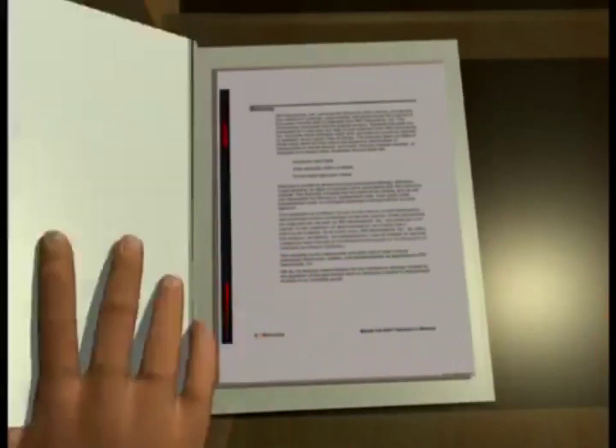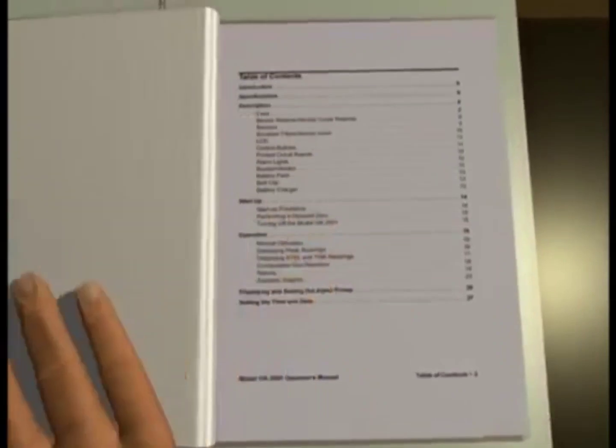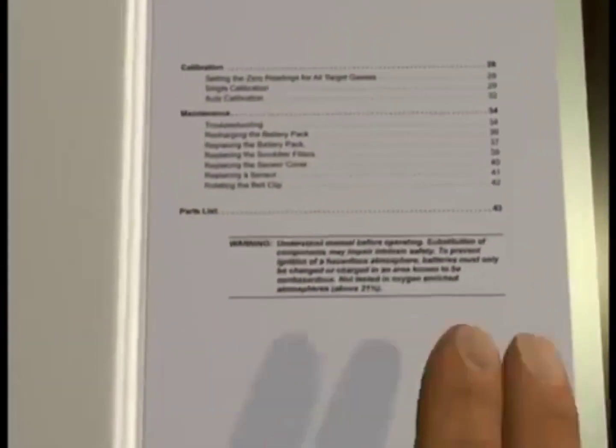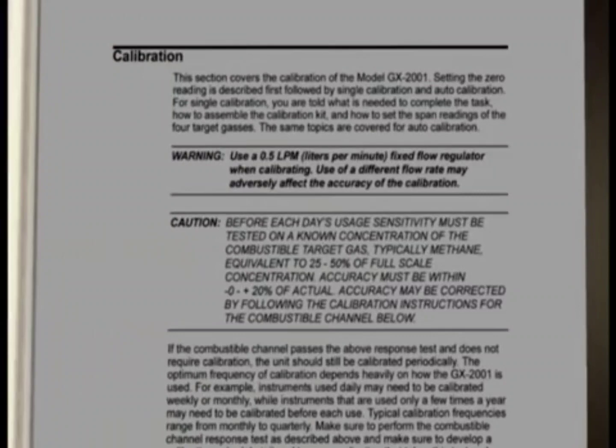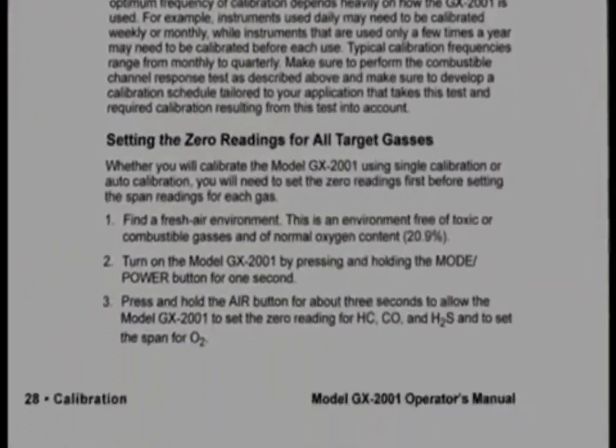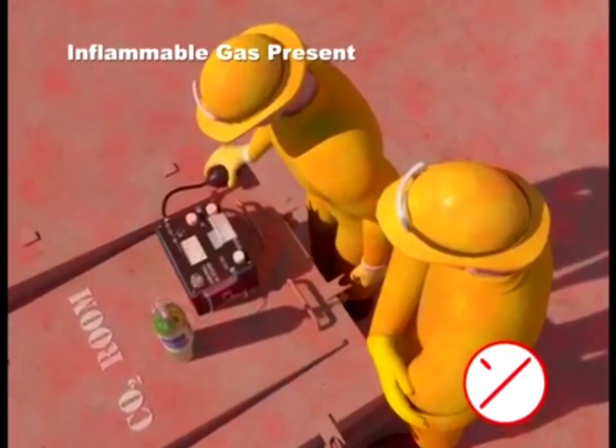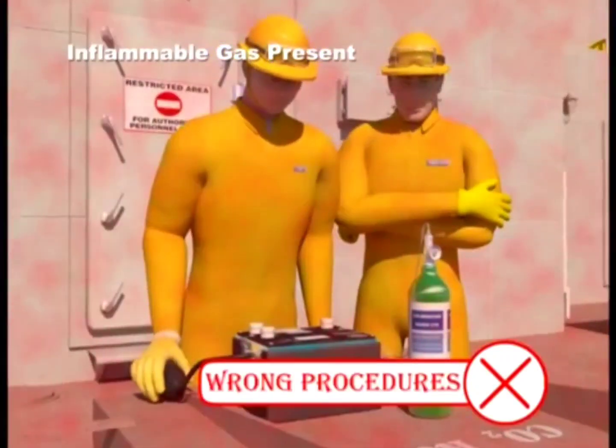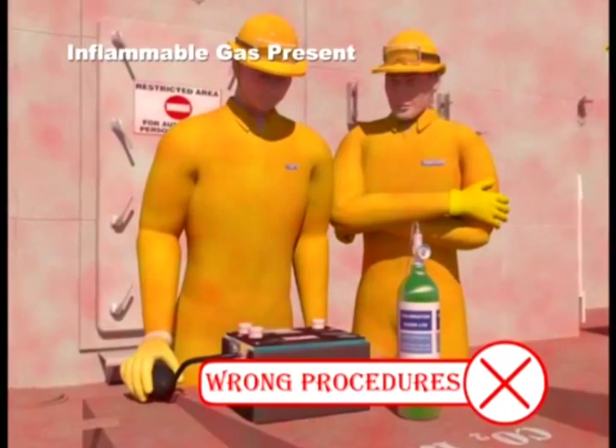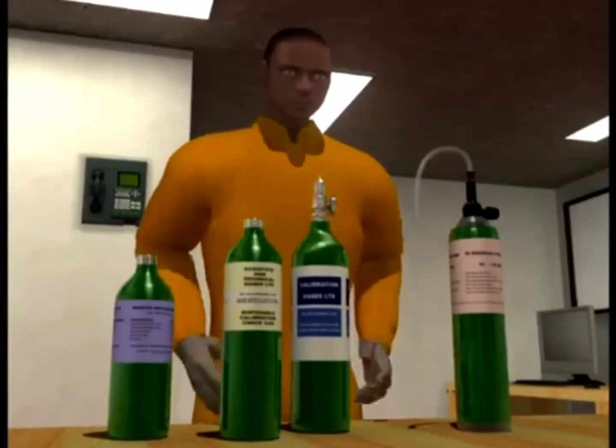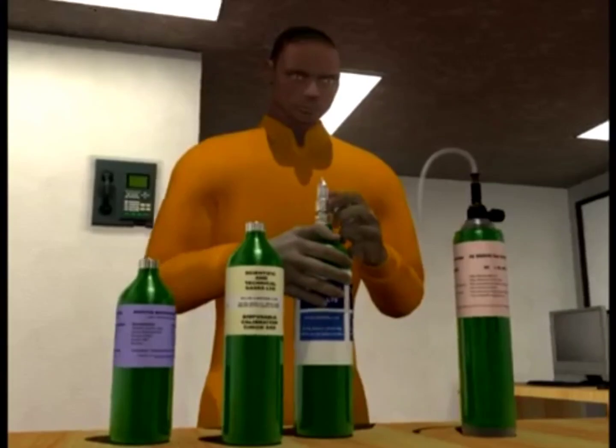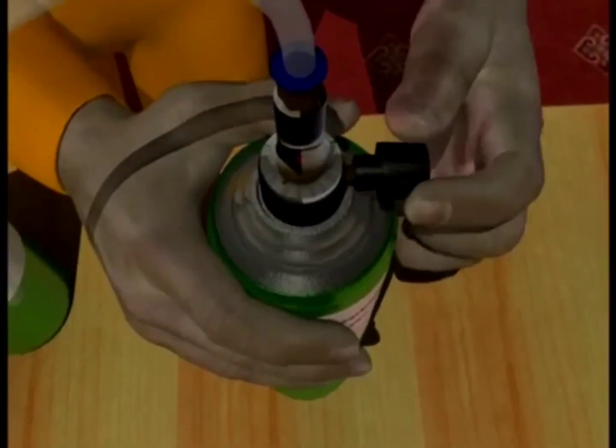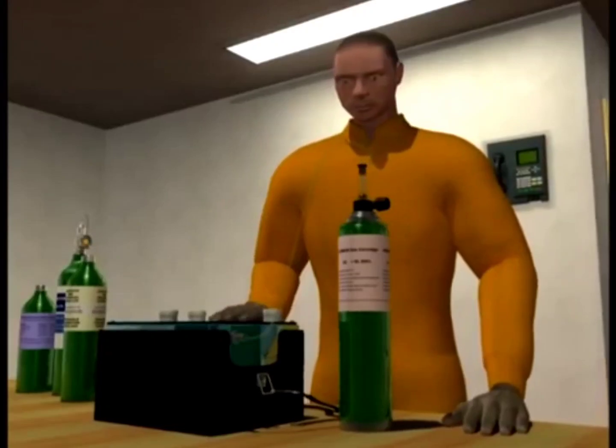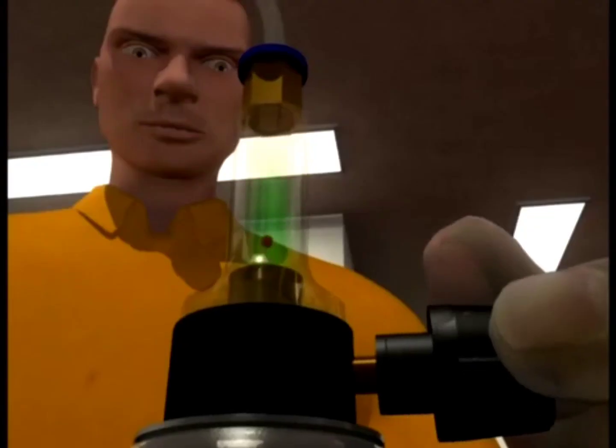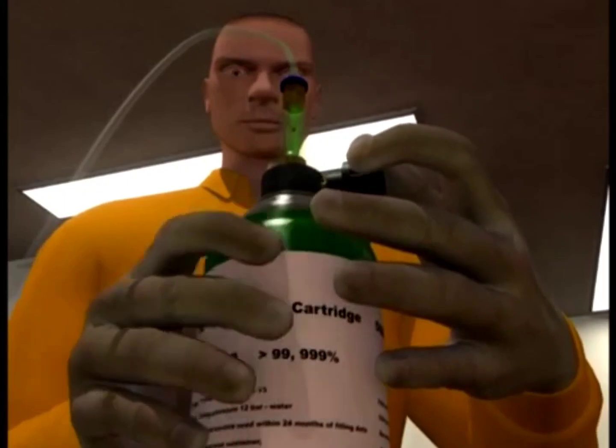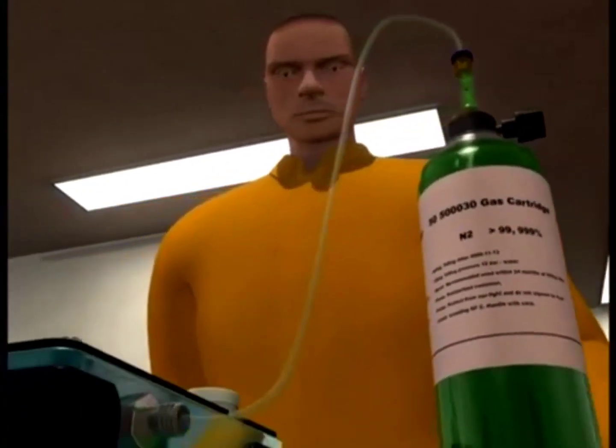The correct calibration procedure is available in the manual of the equipment. However, a standard procedure would appear as follows. No calibration should ever be undertaken in an area having possibility of inflammable gas being present. To calibrate any equipment, fit the correct adapter on the span gas bottle. The span gas may be directly introduced into the meter through a flow control valve, with the knob being adjusted to ensure a slow introduction of the gas.